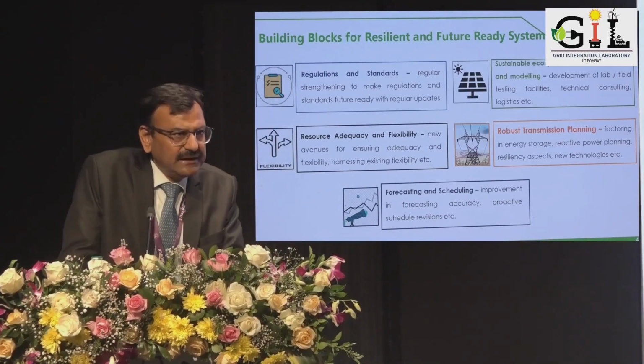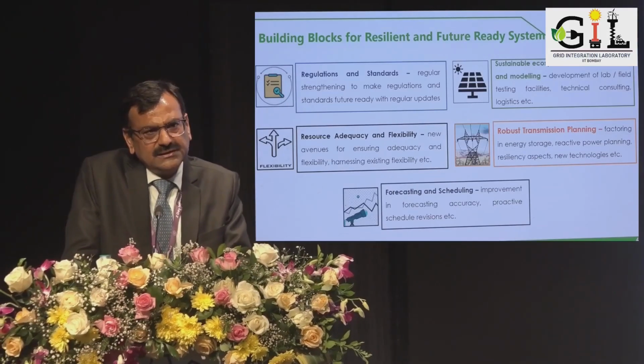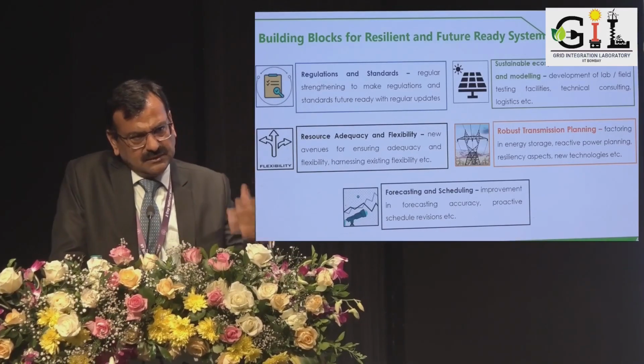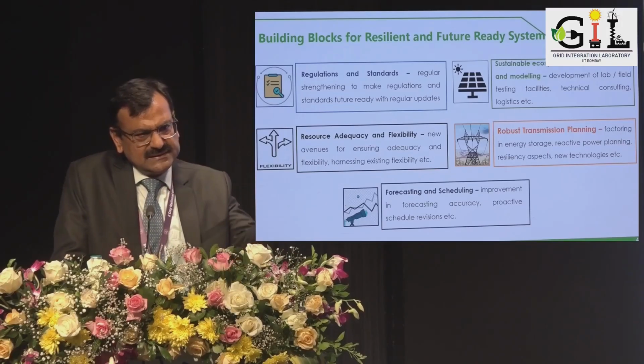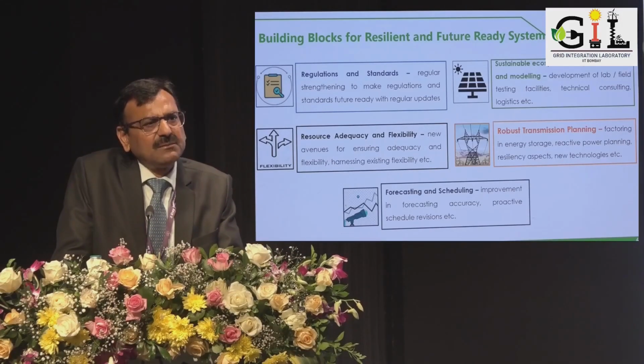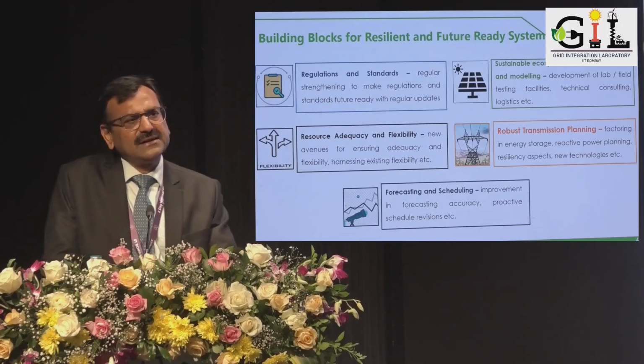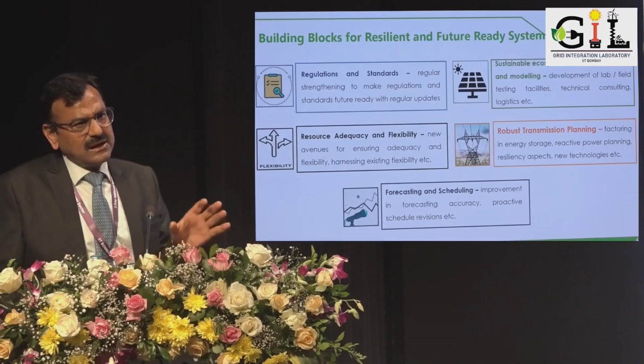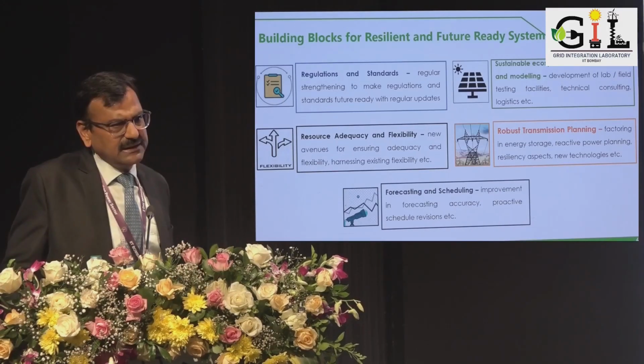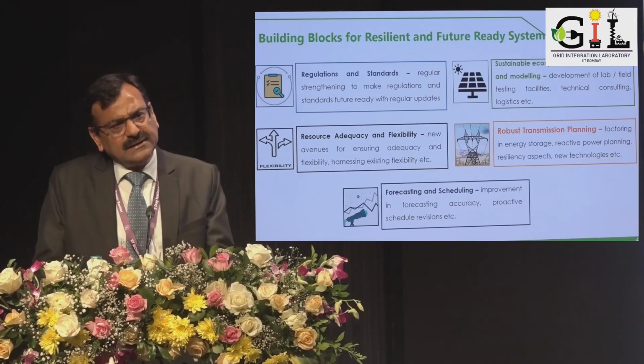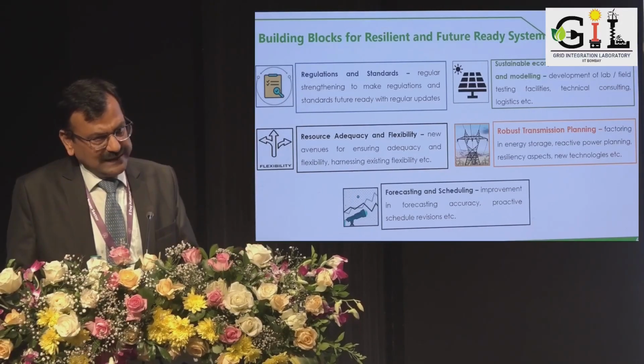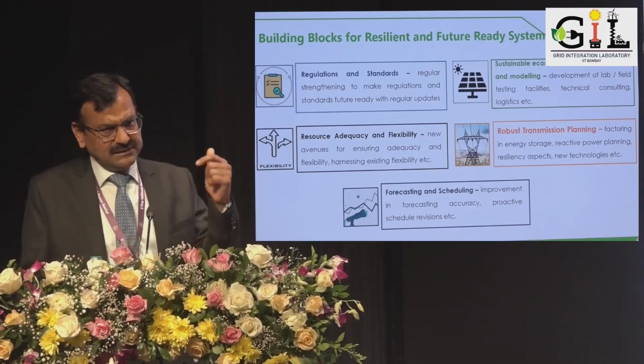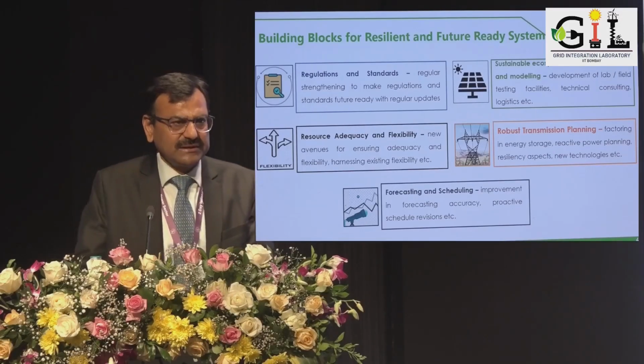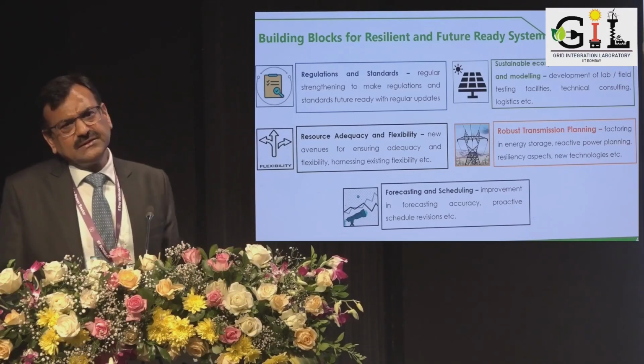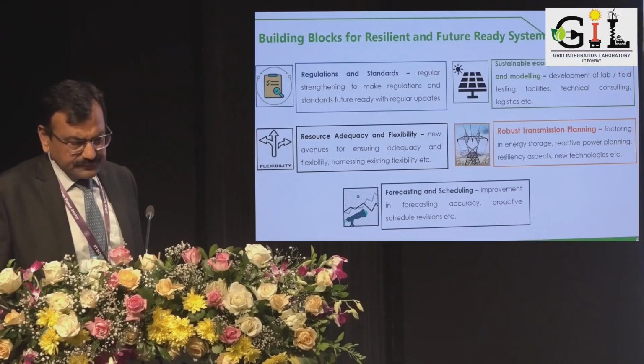So lately there has been a committee formed in the northern region, working in this direction. Some of the actions they have taken: some synchronous condensers are required in the Rajasthan area, some will be installed, and we will move forward in that direction. This will not only give us inertia, but will also improve short circuit strength and further strengthen the reliability of the grid.